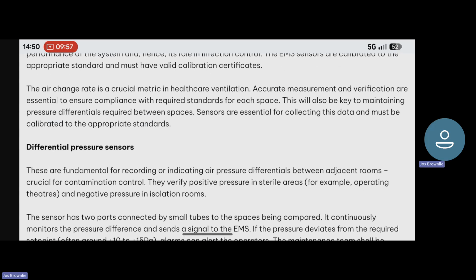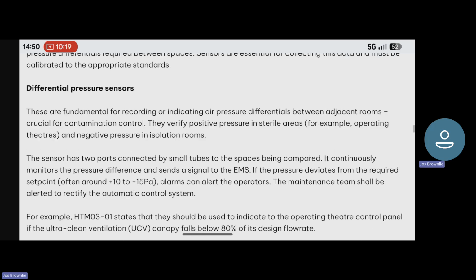The air change rate is a crucial metric in healthcare ventilation. Accurate measurement and verification are essential to ensure compliance with required standards for each space. This will also be key to maintaining pressure differentials required between spaces. Sensors are essential for collecting this data and must be calibrated to the appropriate standards.